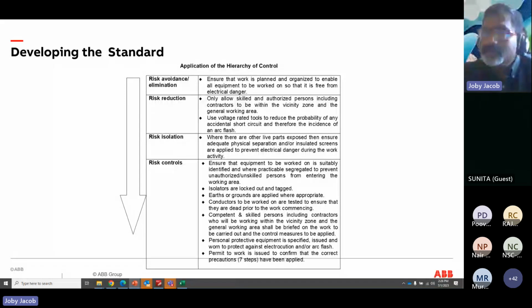Make sure that only skilled, authorized persons work. Non-technical people are not supposed to use voltage rated tools, particularly in a low voltage environment. Isolation: if you can isolate, use remote switching and the like. Risk controls include what we call the 7 steps that save lives, which I will show you: proper isolation, locking out, tagging out, earthing and so on, so that when you are working on a service or maintenance job, you make 100% sure that everything is isolated.